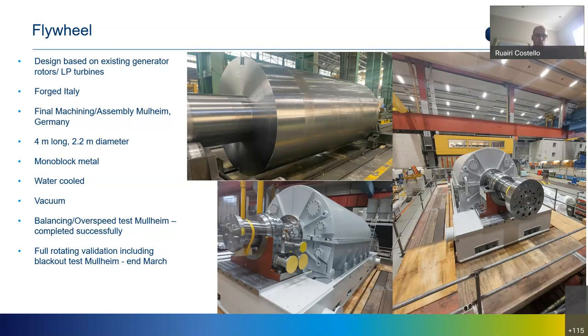Since it was new technology, one of the important things we decided on was an optional price to get a full rotating validation test before we received the unit at Moneypoint. So what will happen there is that Siemens will use a motor and run up the machine in the test pit, run it for a number of hours of stable operation, and then they'll open the breaker and the unit should coast down over a number of hours without power, so on friction alone. And that's due at the end of this month.